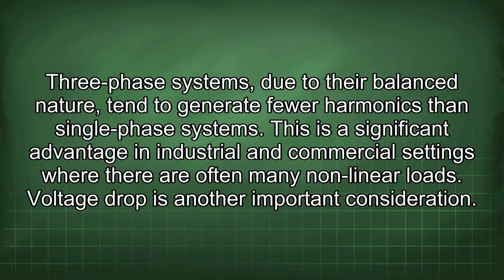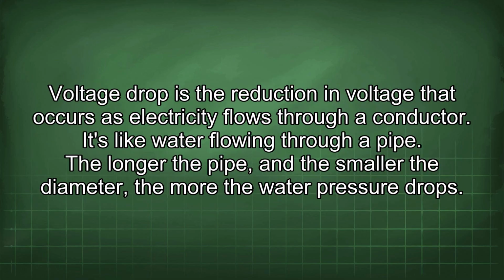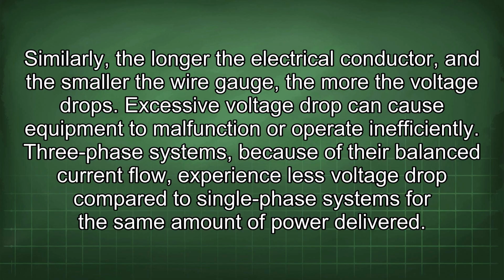Voltage drop is another important consideration. Voltage drop is the reduction in voltage that occurs as electricity flows through a conductor. It's like water flowing through a pipe. The longer the pipe and the smaller the diameter, the more the water pressure drops. Similarly, the longer the electrical conductor and the smaller the wire gauge, the more the voltage drops.